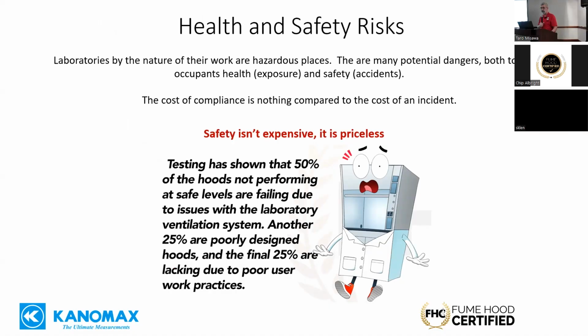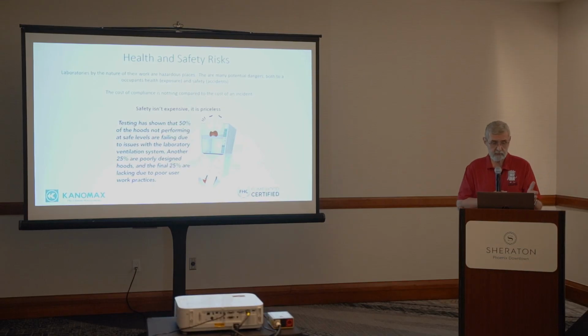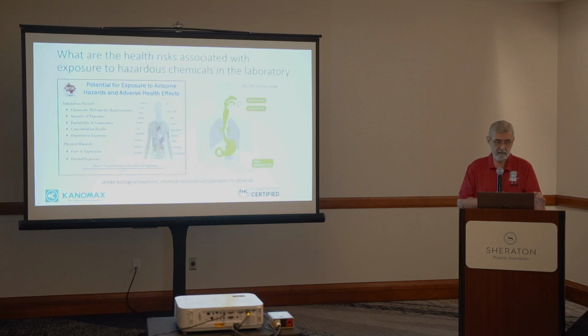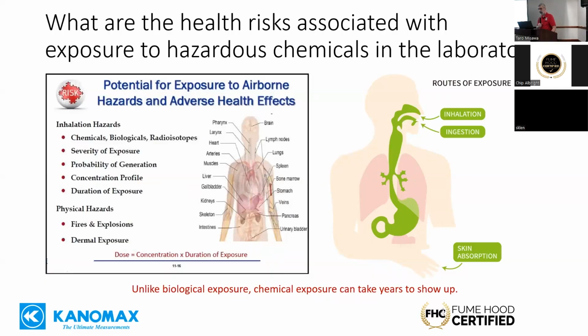It's also been said that safety isn't expensive, it's priceless. Testing has shown that 50% of the hoods not performing at safe levels are failing because of the rest of the ventilation system. So the lab ventilation system is the problem. Another 25% come from poorly designed fume hoods or a poorly laid out laboratory space. And the last 25% comes from worker practices. So the people are part of the system, and we'll look at that. When you look at the health risk, there are three ways to be exposed.